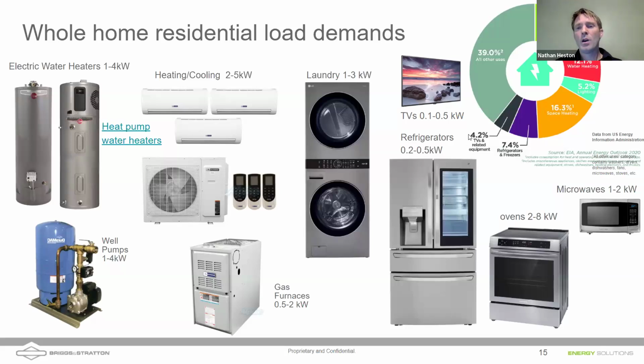I don't have many things on. Televisions are fairly low now, unless you have a plasma TV. They're less than a kilowatt, but electric ranges can be very large, right? Especially when you're running multiple burners at once, you can get up to 8, even 10 kilowatts. Microwaves typically aren't operated very long, so it's not the duration, but the power draw that matters: if you have many devices on at once, they can overload an inverter. In the top right of the screen, I did point out what percentages these different loads take over average US households. This is from the US Energy Information Administration.